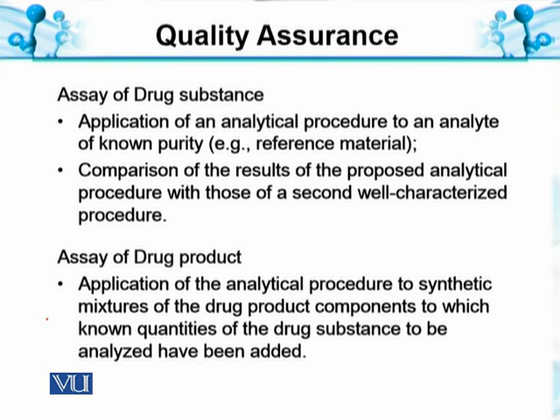For the Assay of Drug Substance, the first approach is the application of the analytical procedure to an analyte of known purity. The second is comparison of the results of the proposed analytical procedure with those of a second, well-characterized procedure — for example, comparing a titration method and a complexometric method with an instrumental method. We also apply the procedure to synthetic mixtures of drug product components to which known quantities of the drug substance to be analyzed have been added, including inactive excipients, to determine analyte concentration.